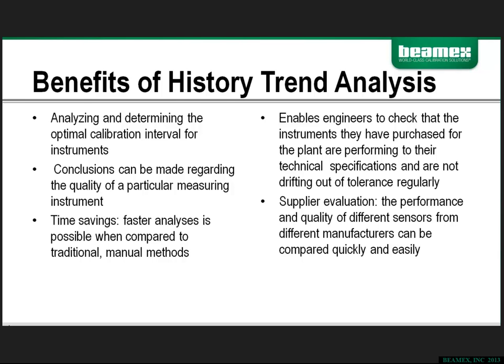But it's going to save you money in terms of not wasting labor by going out and performing actions that would be considered unnecessary, because that particular instrument has shown a history of being able to maintain its tolerance for a longer period of time than just, say, the 6 months that you would normally calibrate it on as a calibration interval. The history trend also will allow you to compare like instruments by different manufacturers to identify the unit that works best or is the most accurate over time.